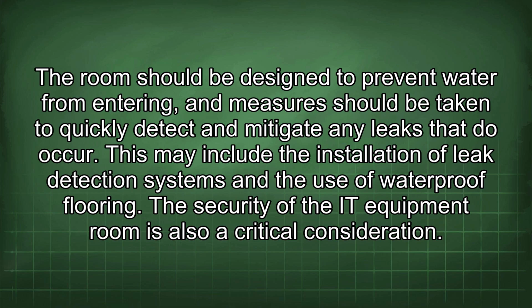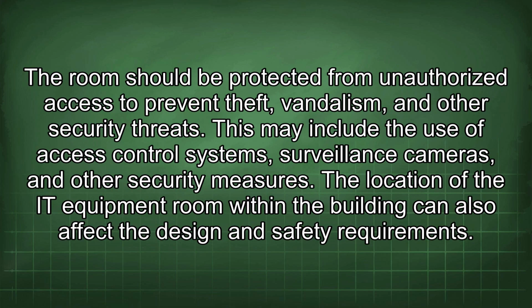The security of the IT equipment room is also a critical consideration. The room should be protected from unauthorized access to prevent theft, vandalism, and other security threats. This may include the use of access control systems, surveillance cameras, and other security measures. The location of the IT equipment room within the building can also affect the design and safety requirements.